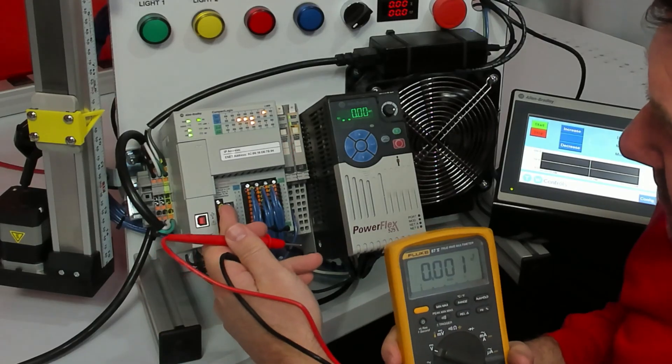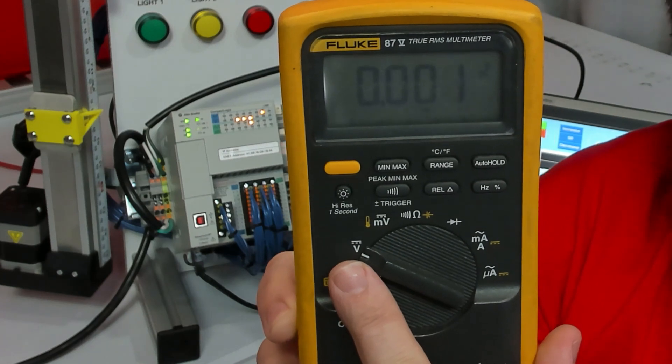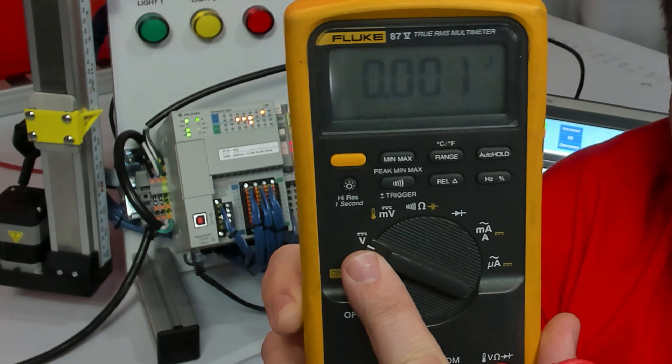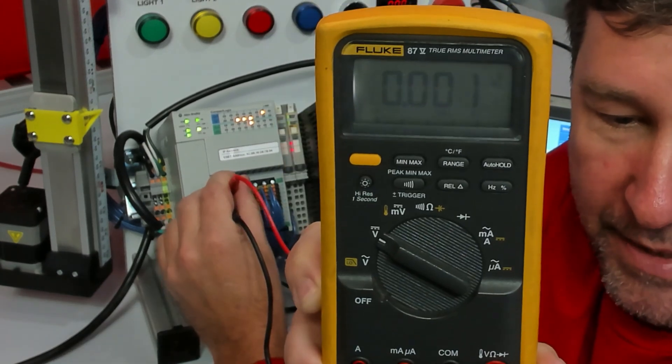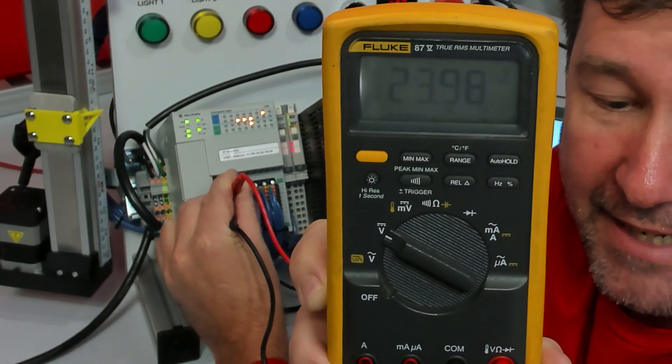Our CompactLogix PLC is powered by 24 volts. I'll set my meter to volts DC, and you can tell it is DC because that's a solid line with a dash underneath it. When I check the CompactLogix power supply, I get 23.98 volts.